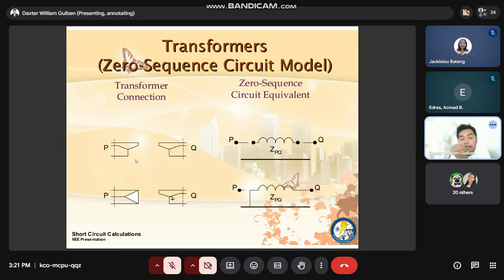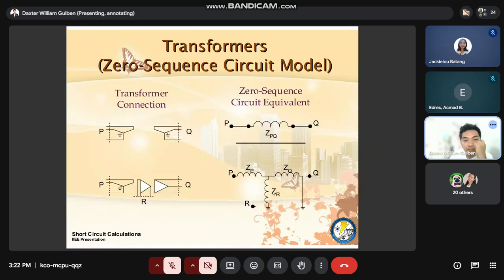Now, if you have an ungrounded and ungrounded Y, again your transformer is isolated. But if delta to grounded Y, you have to connect your delta side at the reference, then continue to the Q. If grounded to grounded, it's just a typical impedance. Again, this is only applicable to the zero sequence network. Then this is for the three winding.